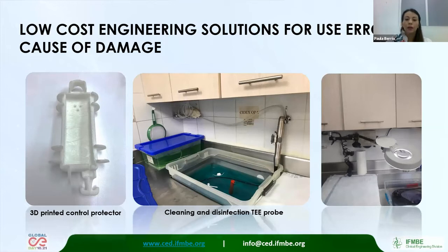Another measure we had is that we implemented a quick guide and accessories for cleaning and disinfection of TEE probes in our sterilization process, because we noticed we have many damages of our TEE probes related to spills and inadequate manipulations from users.